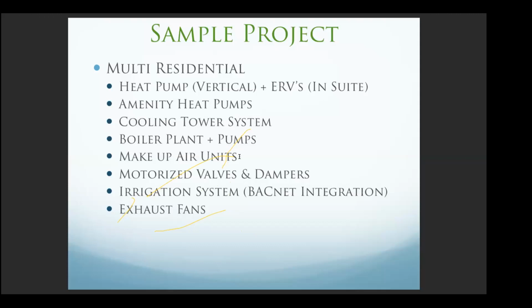Makeup air units, depending on the unit, may come with a BACnet card or just a terminal strip. We may need to put on a controller, hardwire all the points, and field install all the sensors that are being shipped loose by the factory. Motorized valves and dampers, same thing, analog output versus binary output. If there's a feedback, then we need to account for that point as well. That tells us if we've told the actuator to open up X percentage, then it tells us what percentage the actuator has ended up opening at.